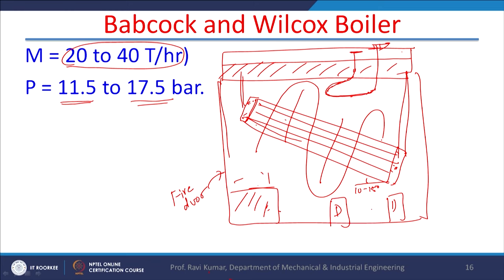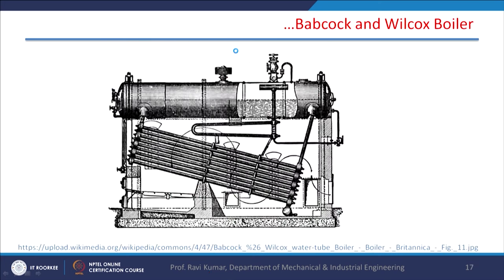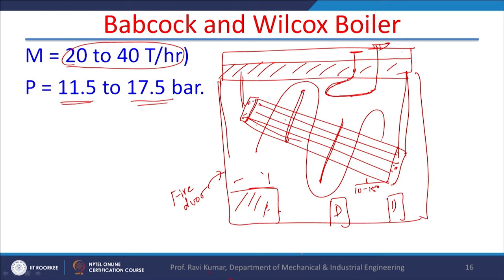It is a very big boiler and has a number of doors for inspection purposes, along with pressure gauges and mountings provided on the shell for monitoring and operation. The inclined tubes can be seen in the schematic; there is a superheater taking steam from the drum. The main attraction of this boiler is it can maintain pressure between 11.5 to 17.5 bar, it can supply superheated steam, and the steam generation rate is quite high at 20 to 40 tons per hour. So I have explained these four classical boilers — that is all for today. In the next class we will take up high pressure boilers. Thank you.